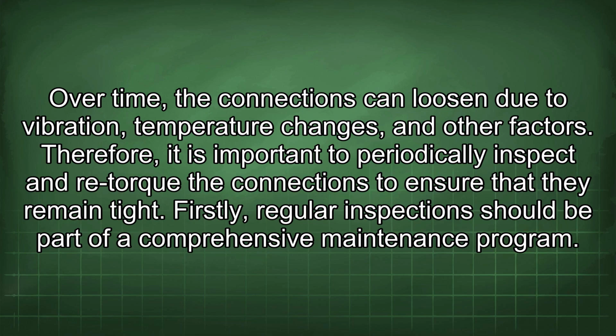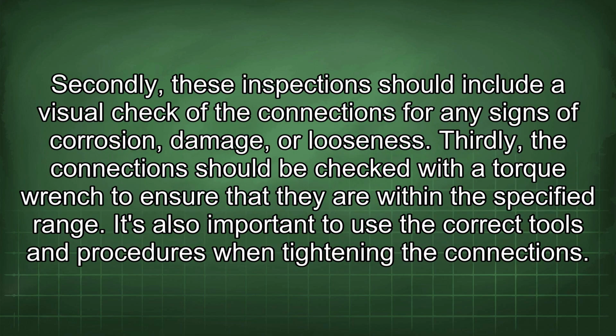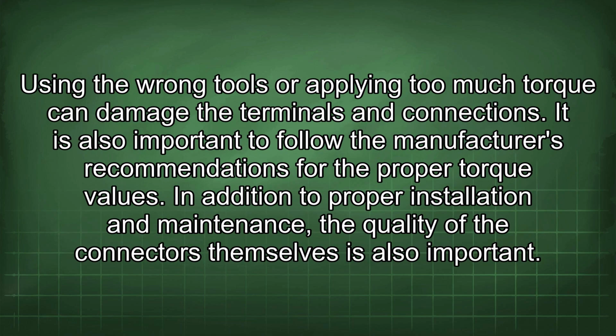Firstly, regular inspections should be part of a comprehensive maintenance program. Secondly, these inspections should include a visual check of the connections for any signs of corrosion, damage, or looseness. Thirdly, the connections should be checked with a torque wrench to ensure that they are within the specified range. It's also important to use the correct tools and procedures when tightening the connections. Using the wrong tools or applying too much torque can damage the terminals and connections. It is also important to follow the manufacturer's recommendations for the proper torque values.